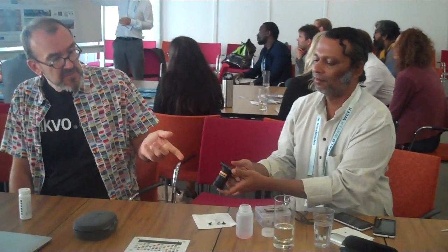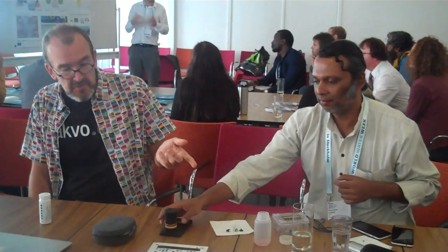It actually takes six photographs using the application, and it goes blip, and then it takes a photograph. It takes a little bit of time between them because we found out that if we took them really rapidly, we heated up the CCD, the actual thing that records the photograph. We heated it up from the flash, and it changed the way it reads colors. So we had to give it a bit of time to cool down.